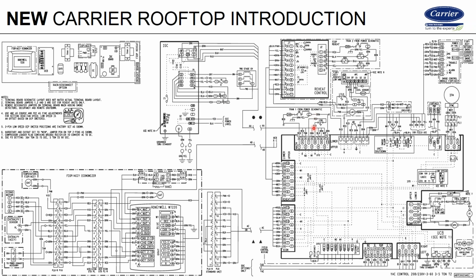Now what we do now, and I'll show you schematically, then we'll go back and look at the picture again, is we take this limit circuit off that blower housing. We leave the limit there, but now we take this circuit and we wire it in series with the other limit right here. So we series wire that together. Now if this one trips or this one trips on high temperature above 160 degrees, now the IGC will collect that information and start flashing a fault code.